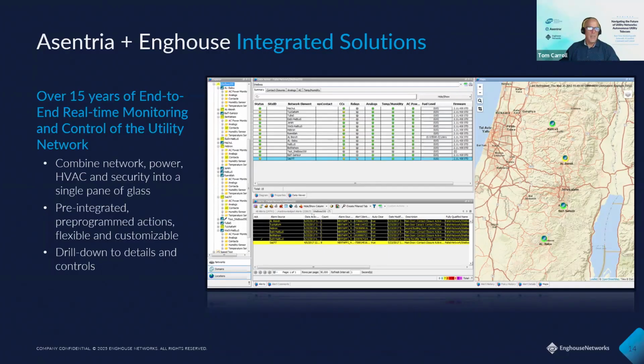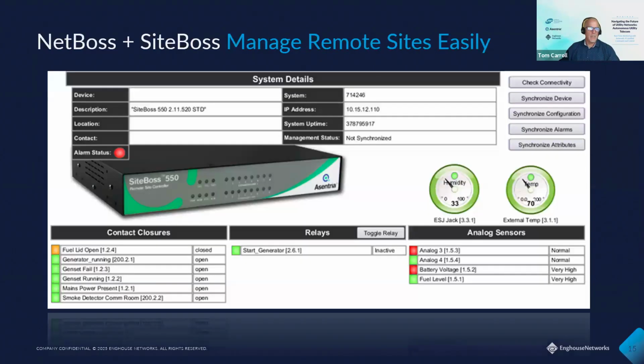Let's look at a drill down real quick. Here's what that looks like. Notice we have interactive buttons here that are pre-programmed to toggle relays or synchronize alarms. You need something like that if you have a network outage to the site, or you're installing new equipment and want to synchronize outstanding alarms. That's what these are for, and they also provide additional details on each and every RTU and site.